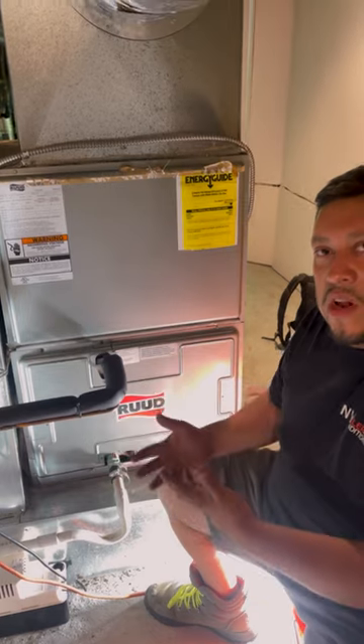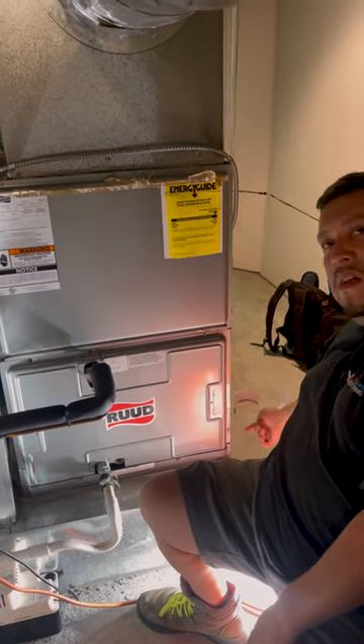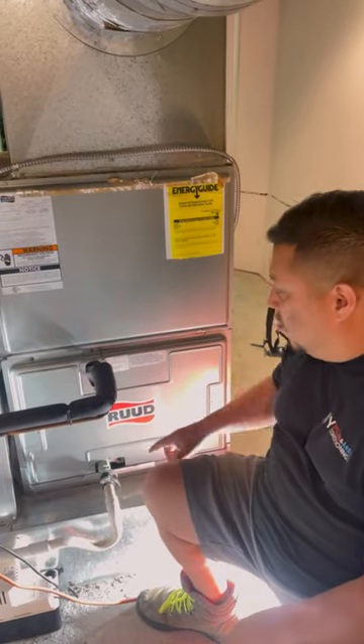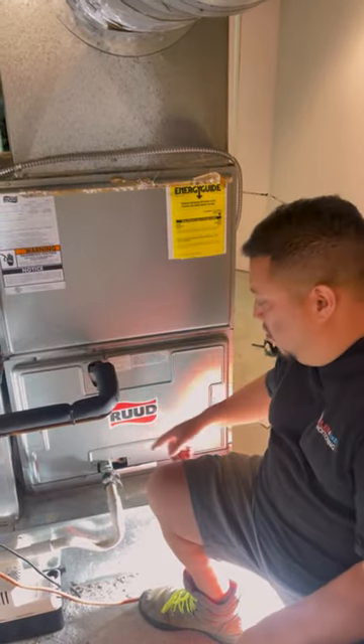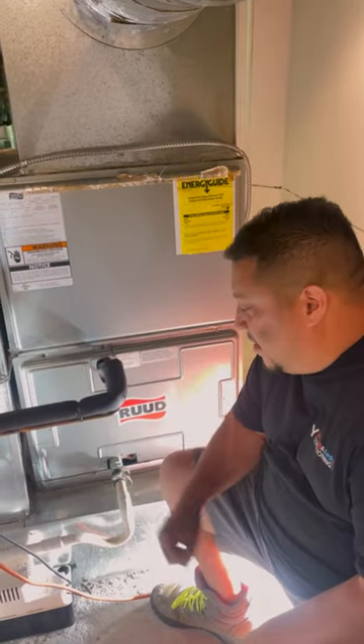So we have several things going on here. We had to clean out the pool of water, so we opened up a hole on the bottom of the box to get some access — we did a little access door. We vacuumed everything out. We also cleaned out the primary pan, cleaned out the trap and the piping, and installed the new condensate pump.